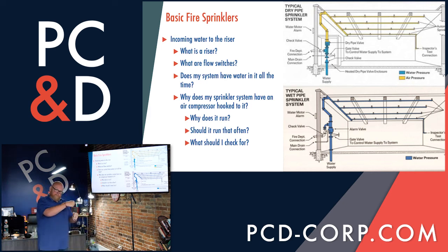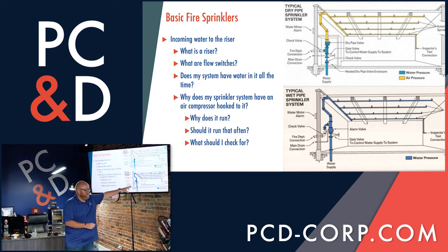As soon as you start to turn that valve and this moves just a millimeter or a fraction of an inch, you have a sensor right here. That sensor will immediately report back to your fire alarm to let you know that someone's tampering with your shutoff valve. So you don't have to worry or be concerned about somebody just coming in and closing your sprinkler system off unbeknownst to you. The fire alarm is going to tell you that.